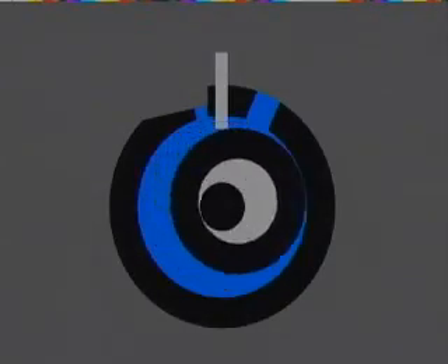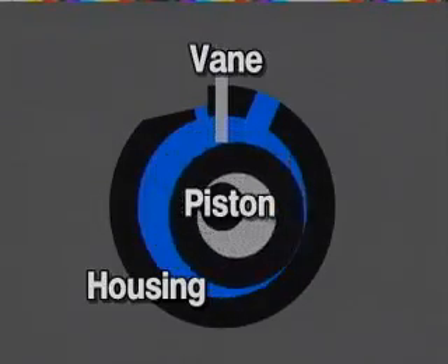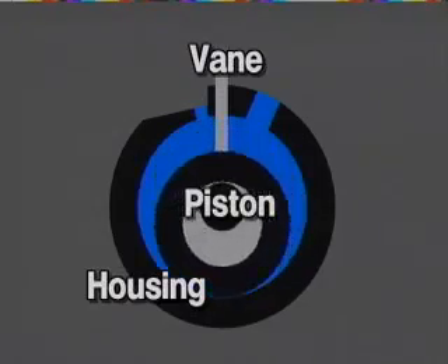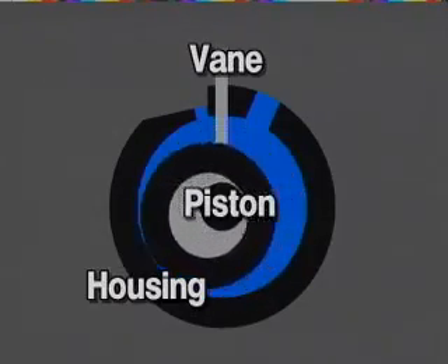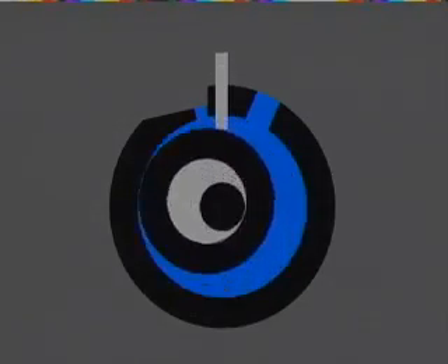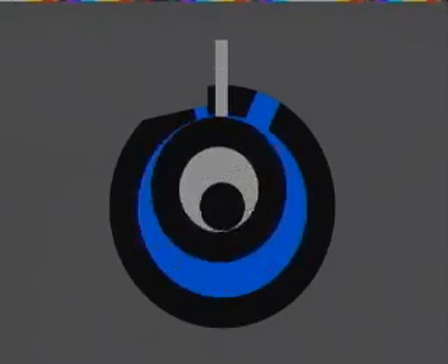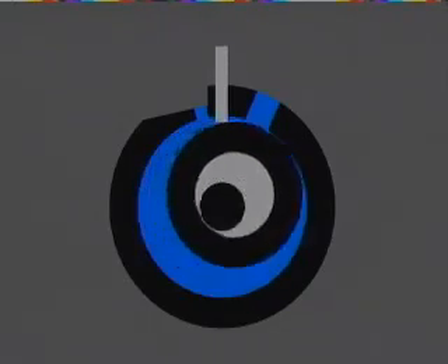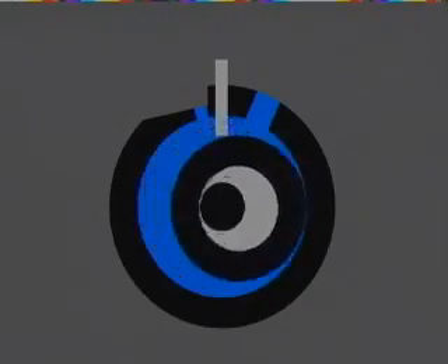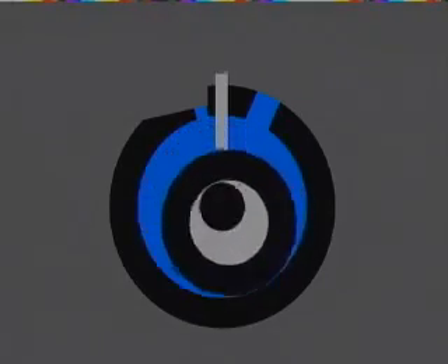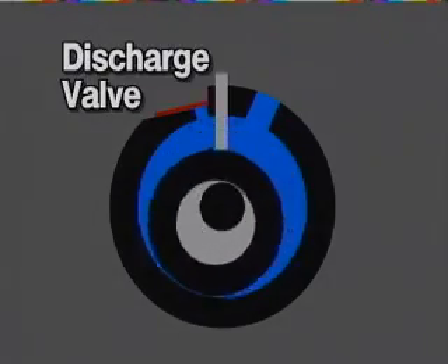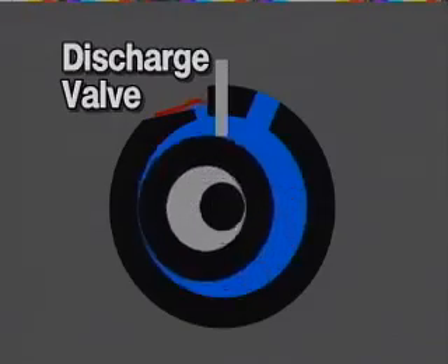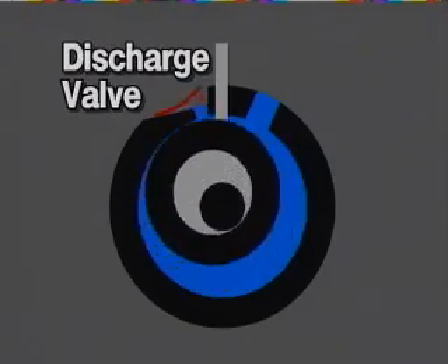A rotary compressor uses a rolling piston within a cylindrical housing to compress vapor against a reciprocating vane. The spring above the vane holds it in contact with the rolling piston at all times, providing a vapor-tight seal between the high and low pressure zones within the compressor. The rotary compressor requires only one valve, the discharge valve.